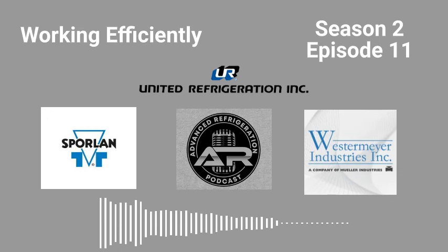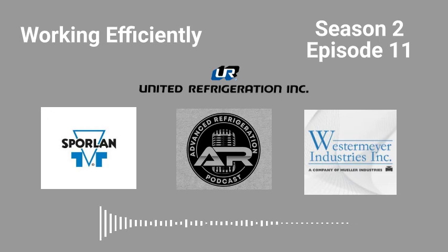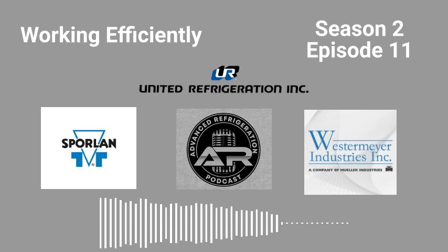When you could do them all at once, at the same time, using Measure Quick, that's quick. So I meant to ask you, on the Measure Quick app, you can use one suction pressure transducer for 3 or 4 temperature sensors, right? So you can basically do a lineup all at once.